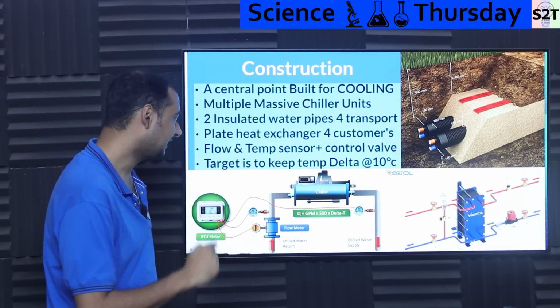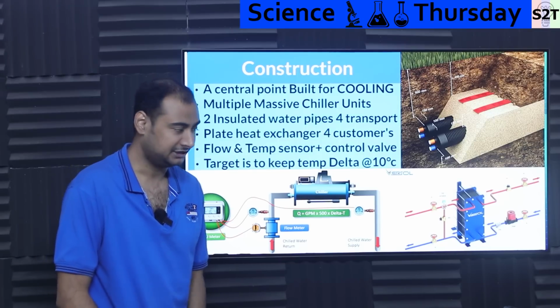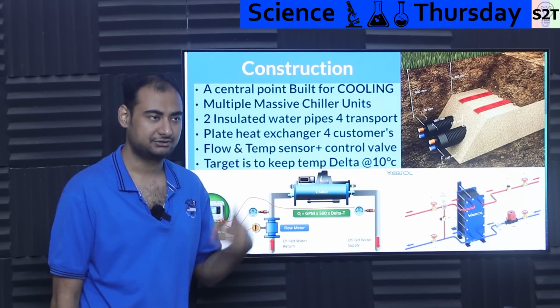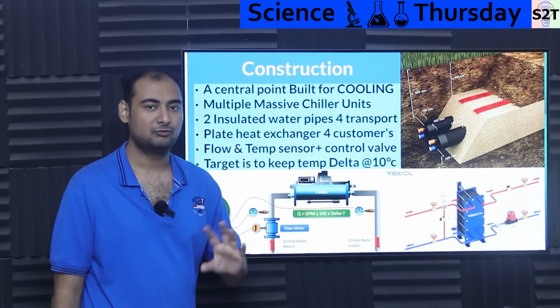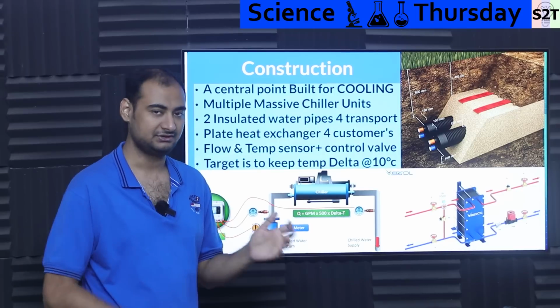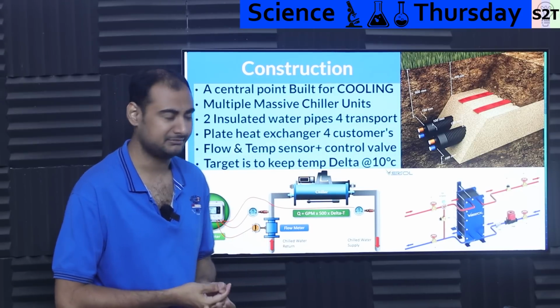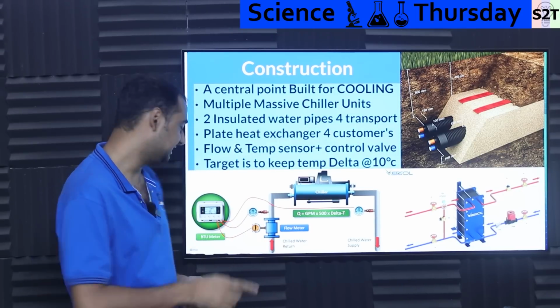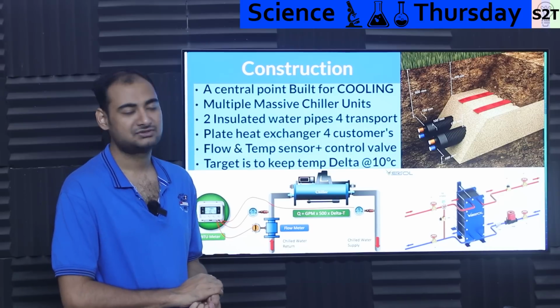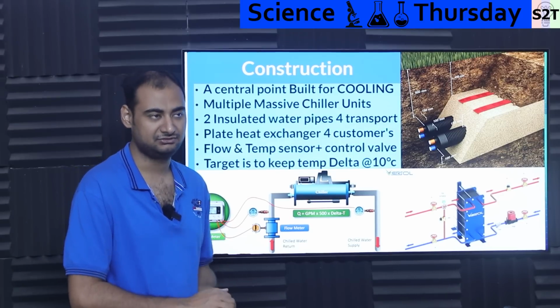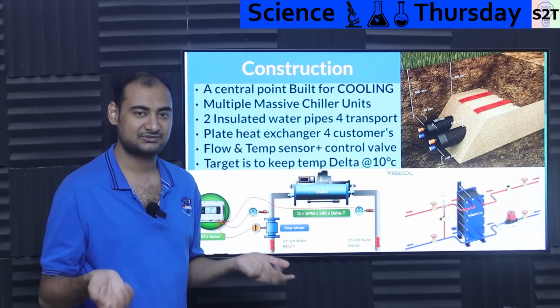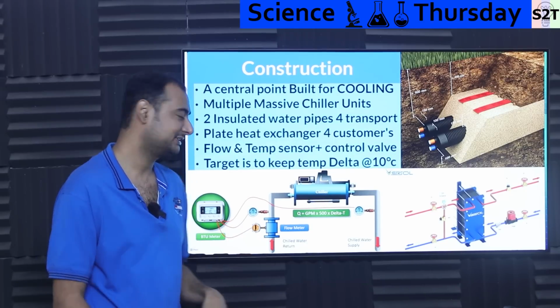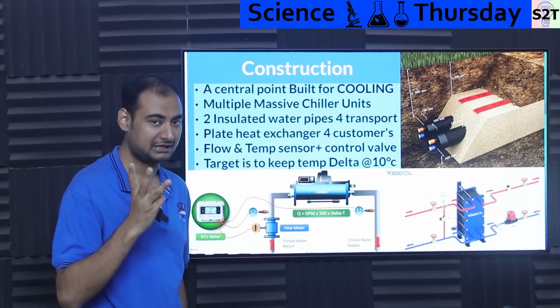After that, how do you get billed? And again, this is not fixed billing. It's not like, okay, you have the system, once per month you get this amount of price. No, it has to be measured based on your requirement. So to do that, we utilize a BTU meter. Do not ask me why we are still using British thermal units of measurement, even though most systems actually use kilowatt, but it is what it is. So you require three primary things.